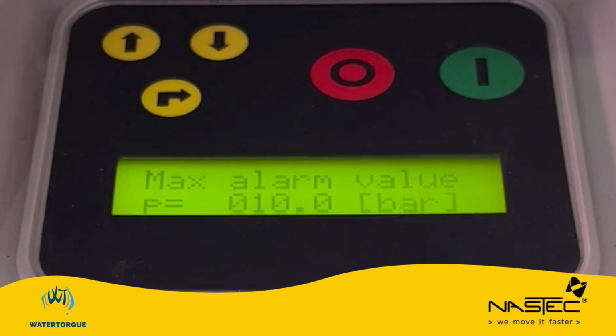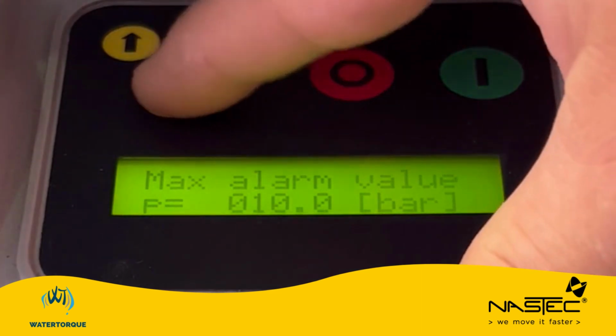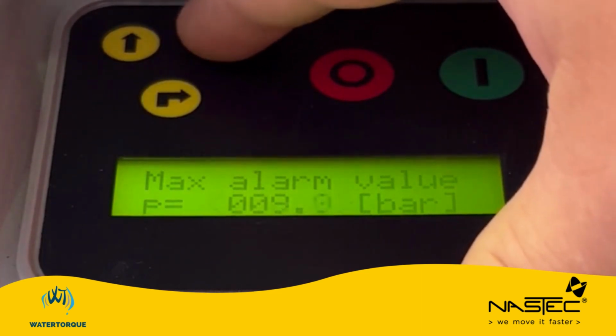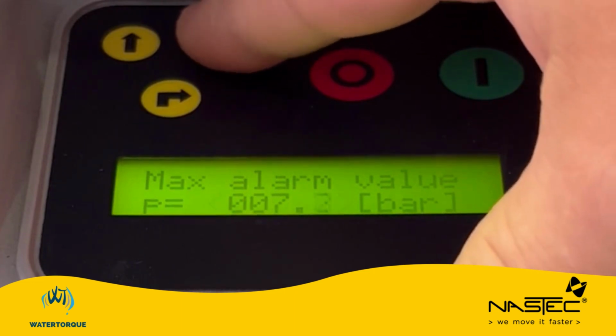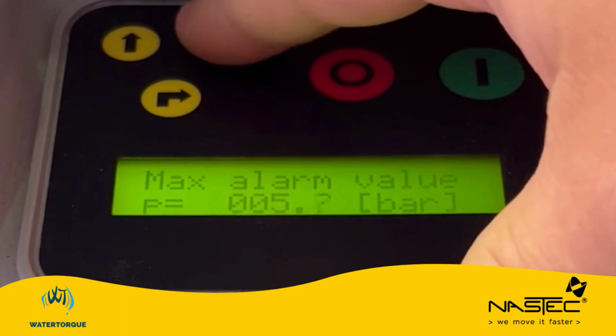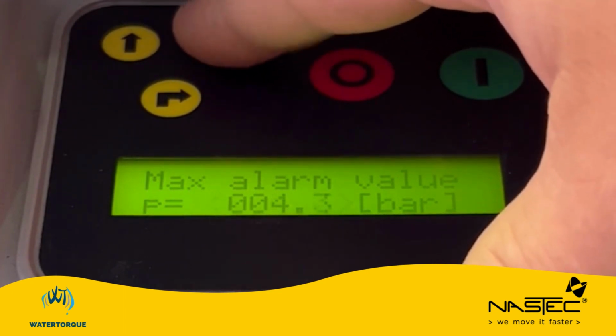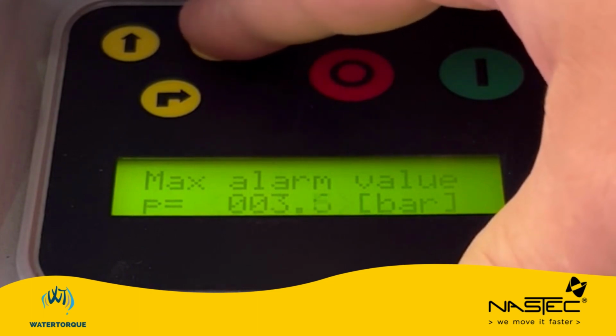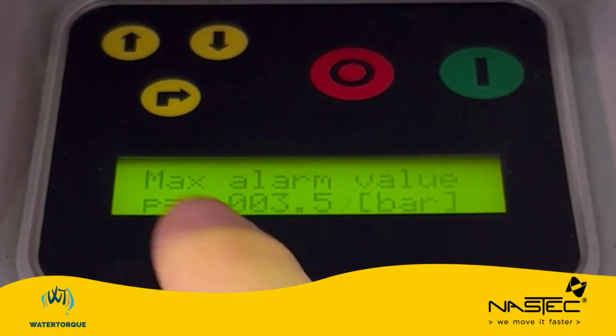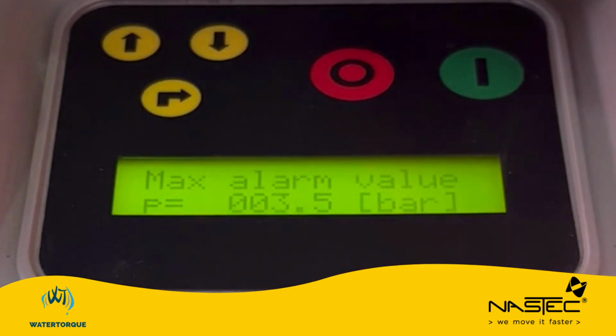For this instance, we will set the constant value as 2.5 bar, and we will set the max alarm value at 3.5 bar. Generally, I would suggest setting your max alarm value at 1 to 1.5 bar over and above your set point value. The way that we do that is we hit the enter button and scroll down until we achieve 3.5 bar. Every site is going to be different, so if you need a hand working out what pressures to input, feel free to reach out to Watertorque. We've got 3.5 bar, we hit the enter button, and that's now locked it in.